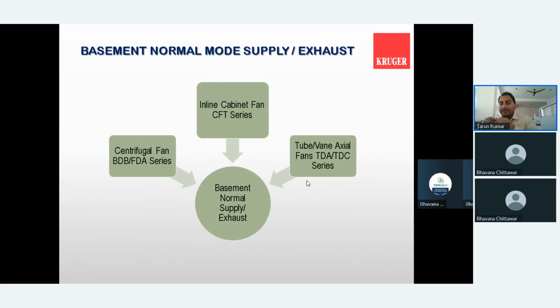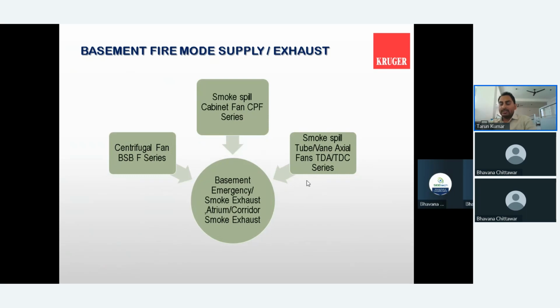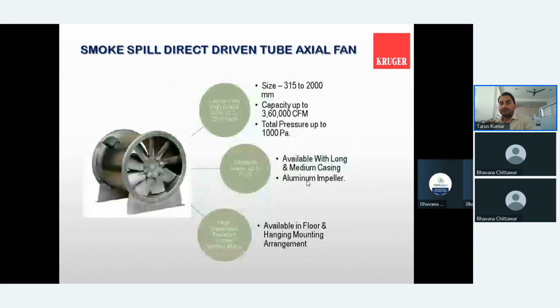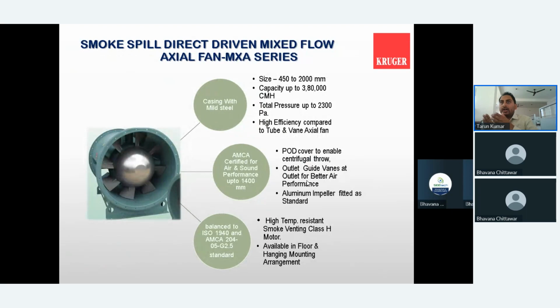There we can also use the cabinet fan as well as the axial fan, and mainly the jet fan, in both the fire mode and the smoke condition. We have the tube axial fan, and further to that we have the vane axial fan. There is a difference between the tube axial fan and the vane axial fan. Both are used for the same purpose, only the efficiency of the fan is a little higher in the vane axial fan. That is the major feature of the vane axial fan, which comes with an additional pod. The efficiency of the fan is higher, it consumes less BKW, and the noise of the fan is very low.